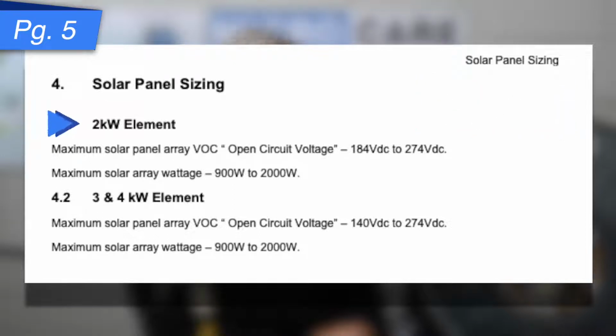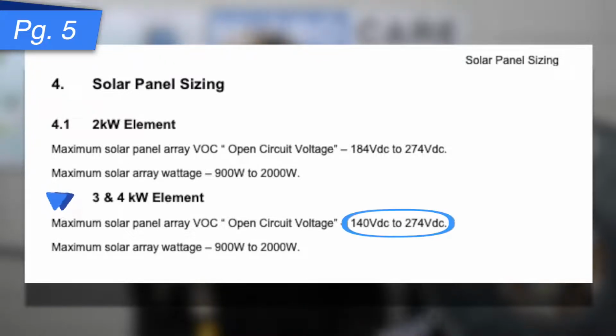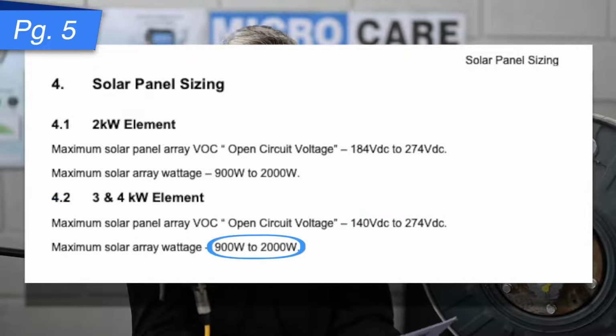Now for the 2 kilowatt element, the voltage window, that means the panels connected in series need to achieve this minimum voltage, which is 184 volts. If you get 174 volts, the unit will work, but it won't heat up the water sufficiently, maybe on a really good day. The max is 274 volts, and that wattage array is from 900 watts to 2000 watts. So an ideal scenario would be something like 900 watts and an open circuit voltage of 200 volts. The 3 and 4 kilowatt element, a little bit of a lower voltage requirement there, from 140 volts up to 274, and the same wattage on the panel.